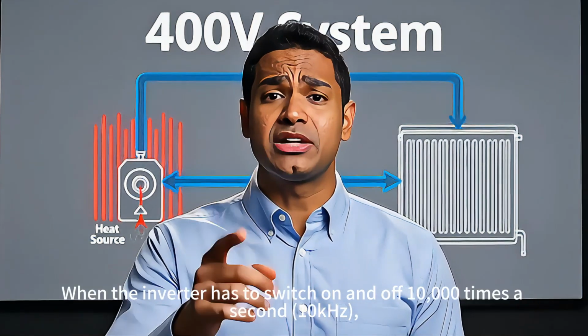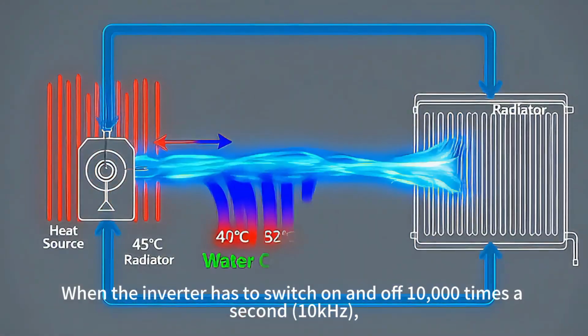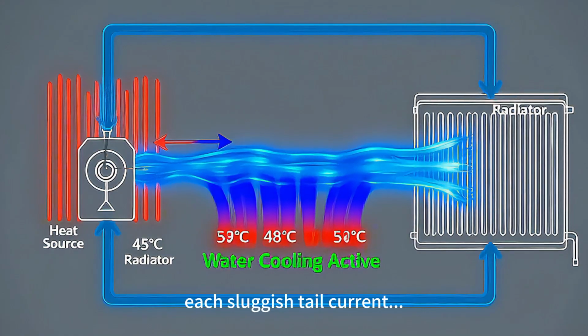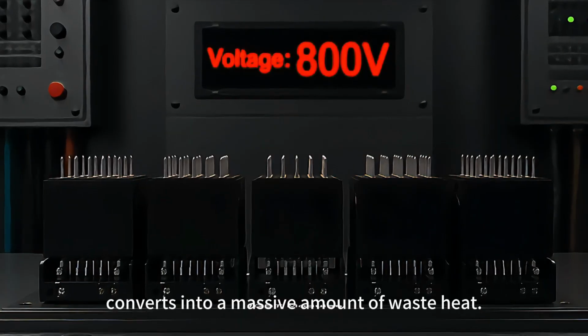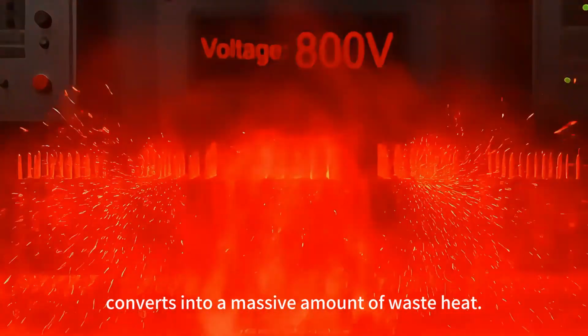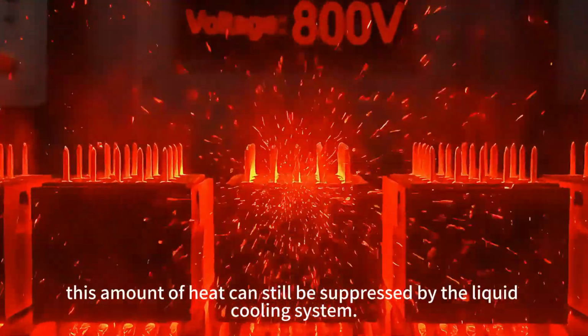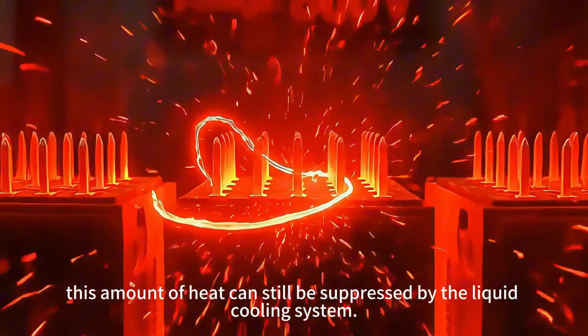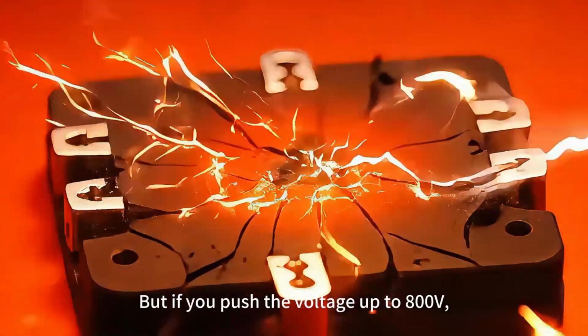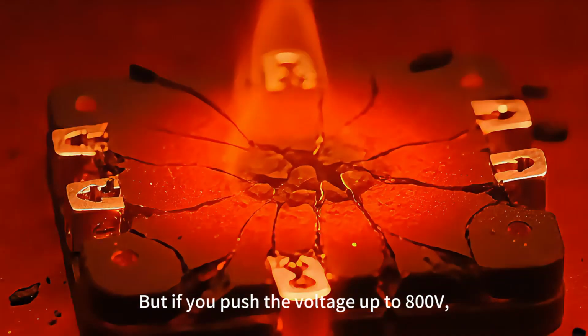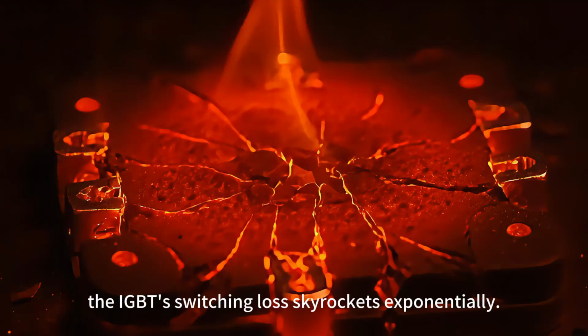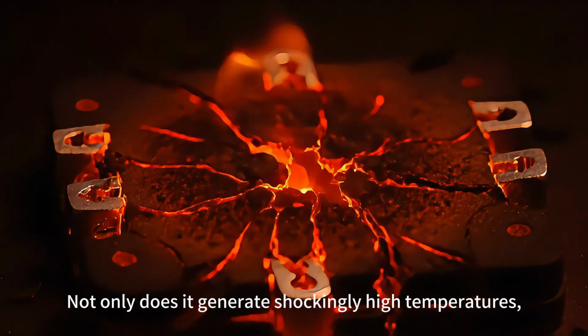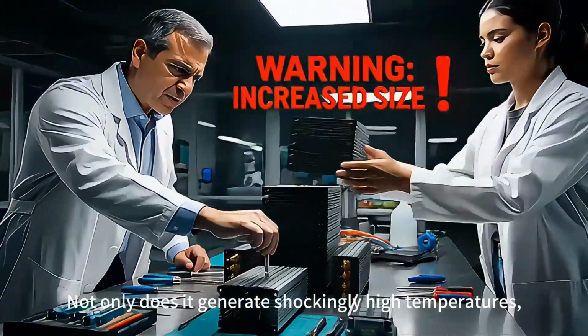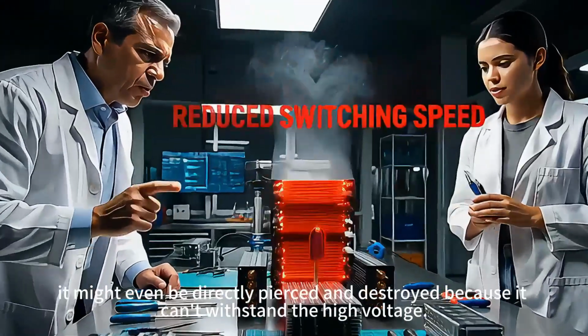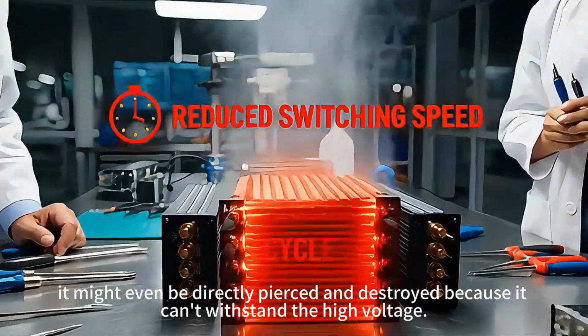When the inverter has to switch on and off 10,000 times a second, 10 kilohertz, each sluggish tail current converts into a massive amount of waste heat. At 400 volts, this heat can still be suppressed by the liquid cooling system. But if you push the voltage up to 800 volts, the IGBT switching loss skyrockets exponentially. Not only does it generate shockingly high temperatures, it might even be directly pierced and destroyed because it can't withstand the high voltage.